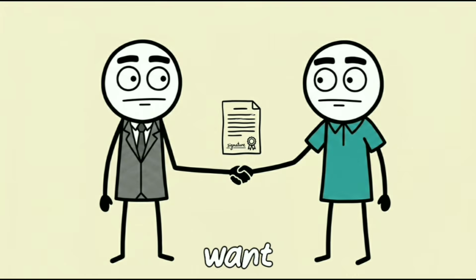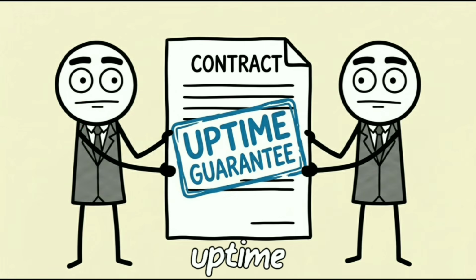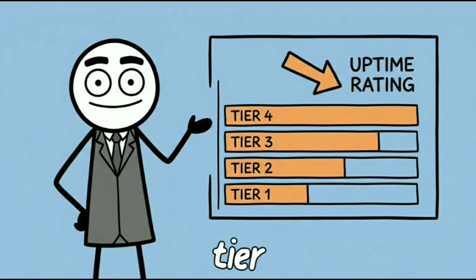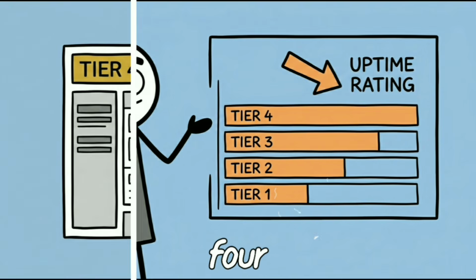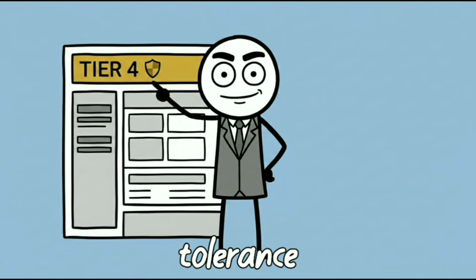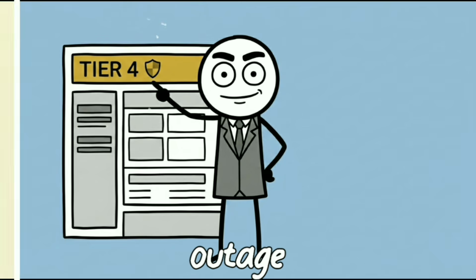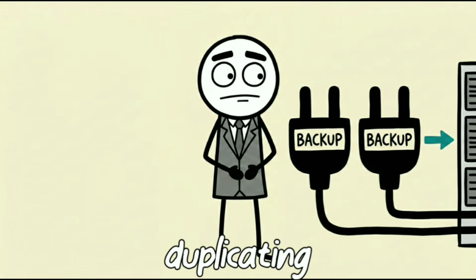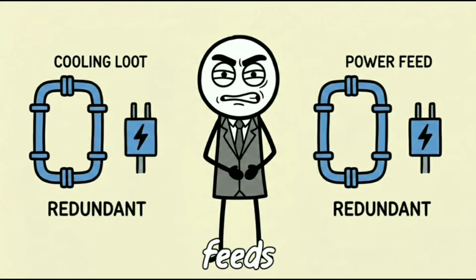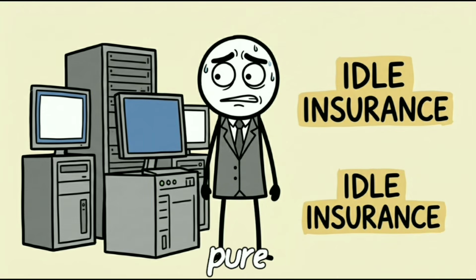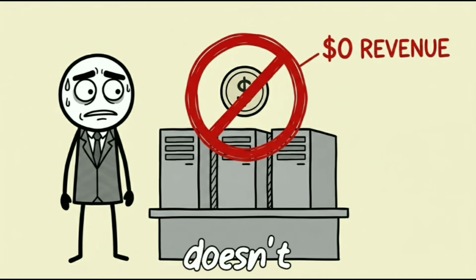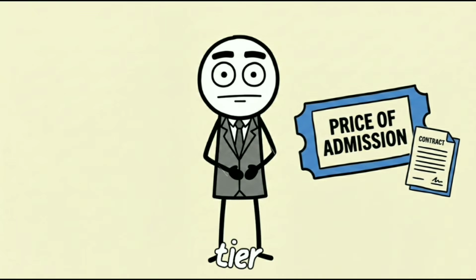Enterprise clients don't just want a lease, they want an audited uptime guarantee, usually expressed as a tier rating from Tier 1 through Tier 4, where Tier 4 promises fault tolerance against literally any single equipment failure without an outage. Chasing that rating means duplicating everything: two power feeds, two cooling loops, two of every critical system, sitting idle as pure insurance. That redundancy doesn't generate a dollar of revenue on its own. It's the price of admission to the tier where the real contracts get signed.